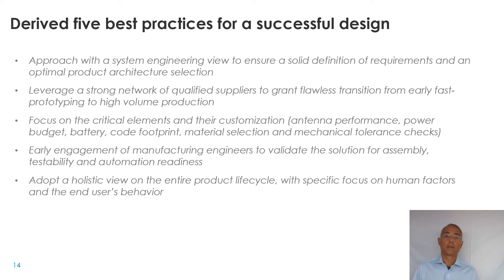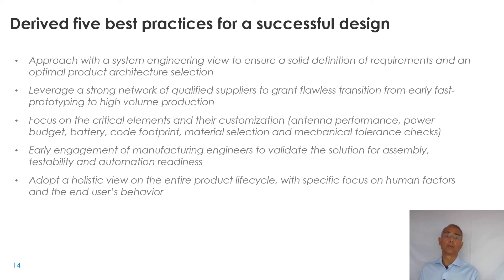Number four: engage manufacturing engineers at the beginning of the design cycle, covering everything that may be needed later in production — testability, assembly, sterilization, and so on. Finally, number five: keep a holistic view on the entire product lifecycle, thinking about environmental conditions during transportation, effects on the electronics and the liquid in the syringe, down to end-of-life dismantling of electronics and battery to meet recycling requirements. And keep a close eye on the user — understand how they will interface with the product with that specific drug, and manage it properly in the design phase.